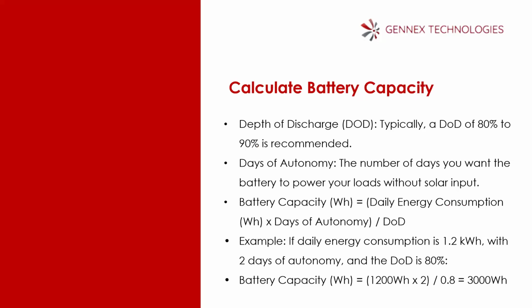The next is to calculate the battery capacity. Depth of discharge, which we call DOD. Typically, a DOD of about 80% to 90% is recommended for lithium-ion batteries. And this does not really harm them. That's why they say it has a deep discharge rate. So, days of autonomy. This means the number of days you want the batteries to power your loads without solar input, just the battery when it's charged. So how long can it power your load continuously without shutting down? That's what it's talking about here.